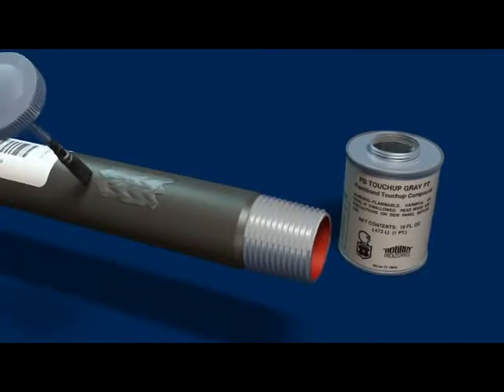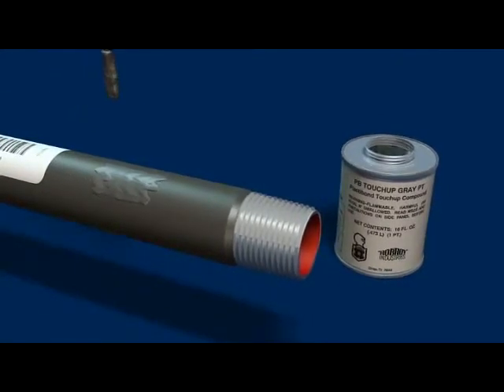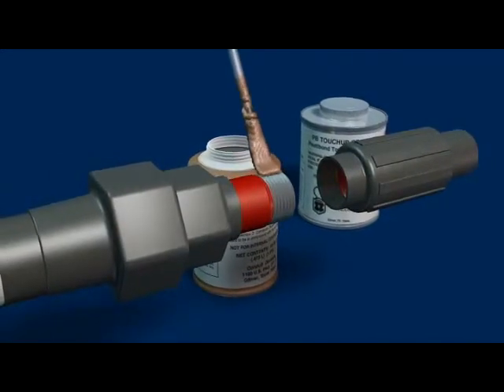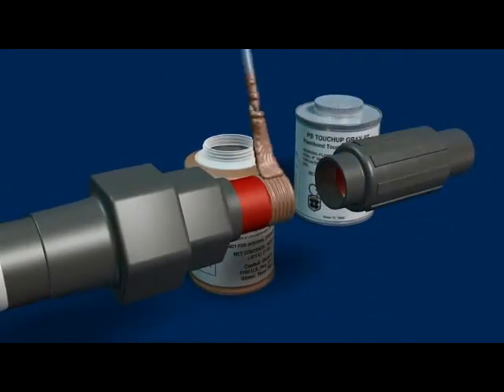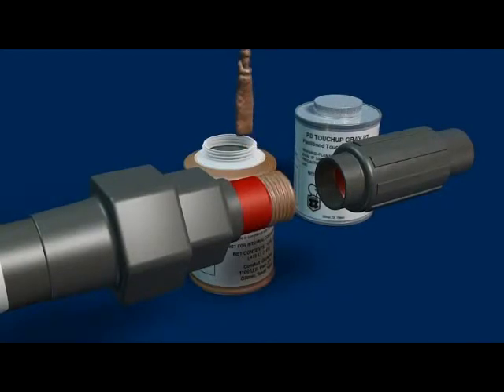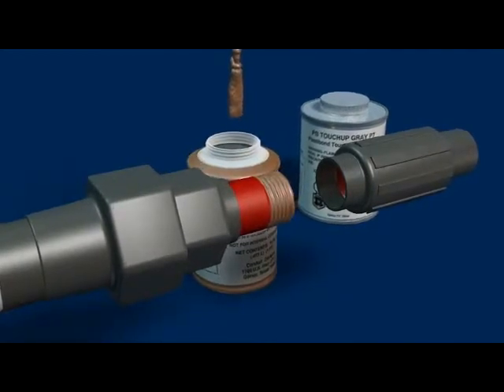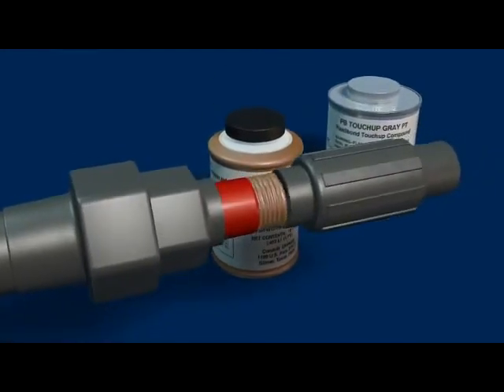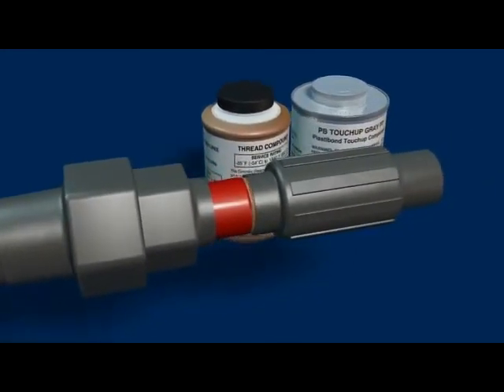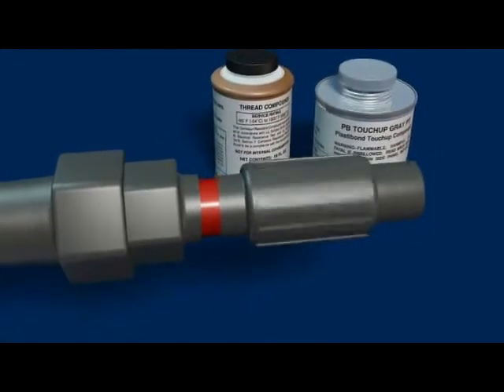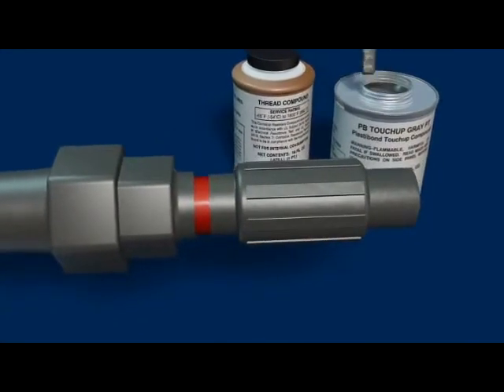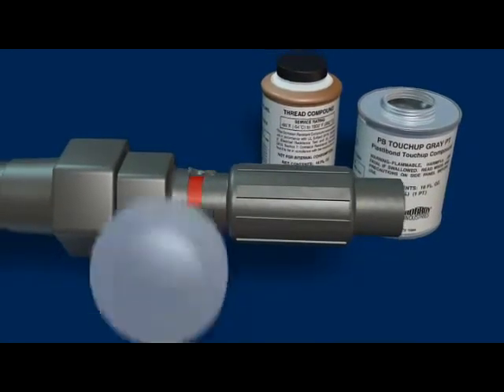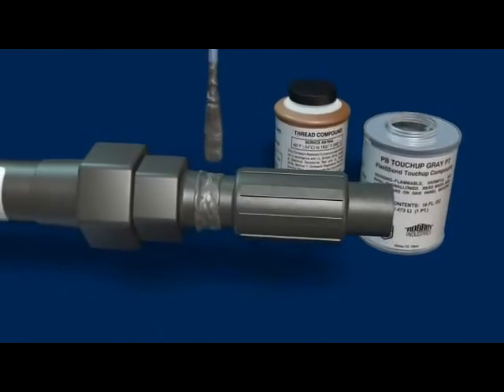Sometimes it may be necessary to apply several coats to obtain adequate coverage. Allow the first coat to dry completely before applying additional coats. Another application for PlastiBond exterior touch-up compound is for use as a sealant at access fitting openings. In wet locations, apply thread compound to factory threads, assemble, then brush touch-up compound over the sleeve joints. PlastiBond exterior touch-up compound is available in pints with a brush tip applicator and in a 13-ounce aerosol can when cosmetic coverage is desired.